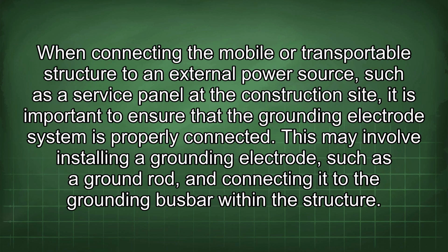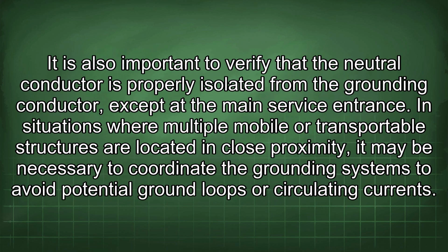When connecting the mobile or transportable structure to an external power source, such as a service panel at the construction site, it is important to ensure that the grounding electrode system is properly connected. This may involve installing a grounding electrode, such as a ground rod, and connecting it to the grounding busbar within the structure. It is also important to verify that the neutral conductor is properly isolated from the grounding conductor except at the main service entrance.